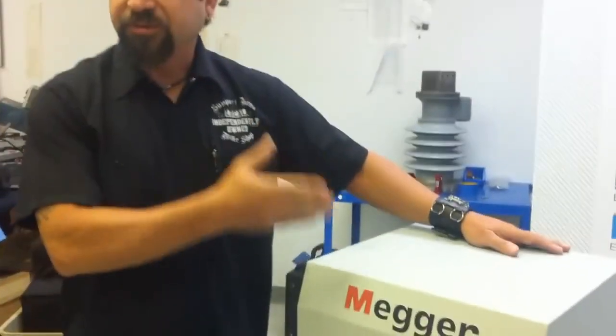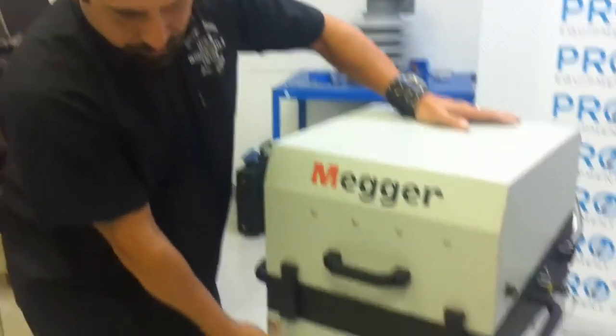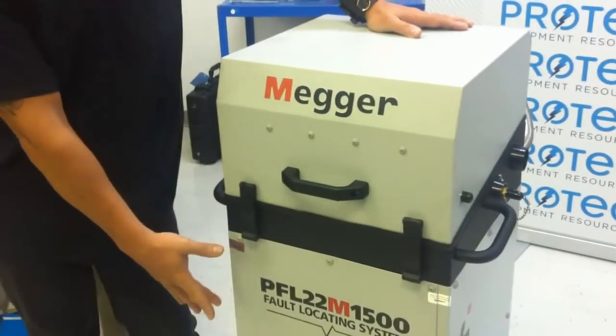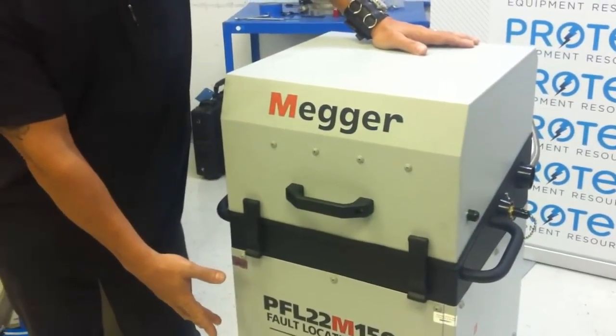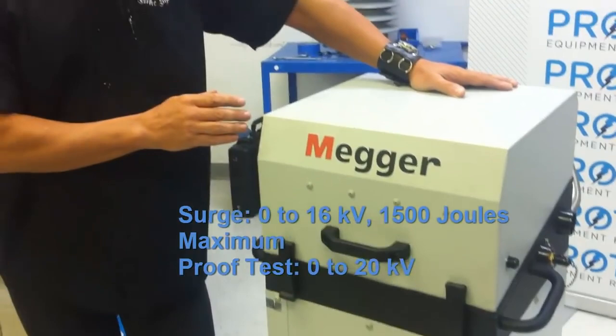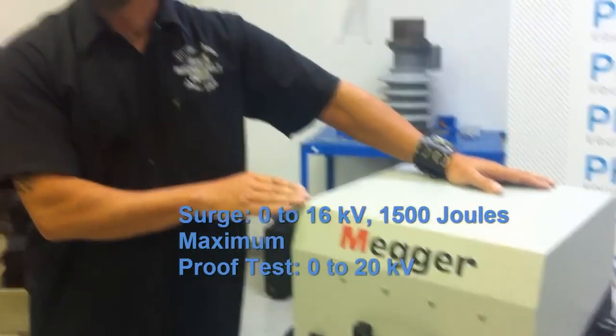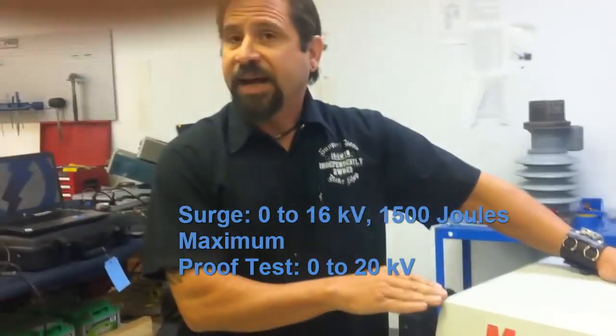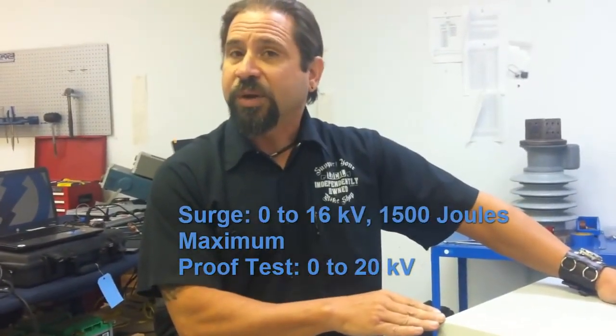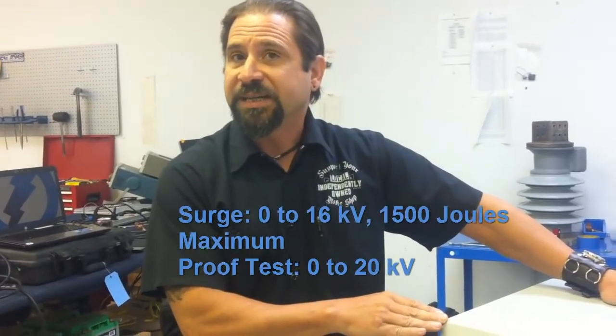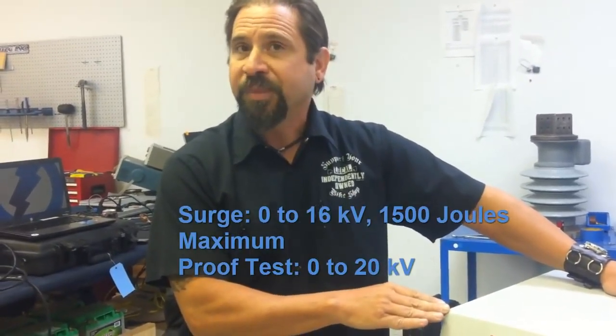Some of the things that I particularly like about this model: it is a completely self-contained instrument. The lower portion comprises your high voltage surge generator. It has an output capacity of 0 to 16,000 volts on surge discharge or thumping. It also has the capability of going 0 to 20,000 volts for doing DC proof testing.